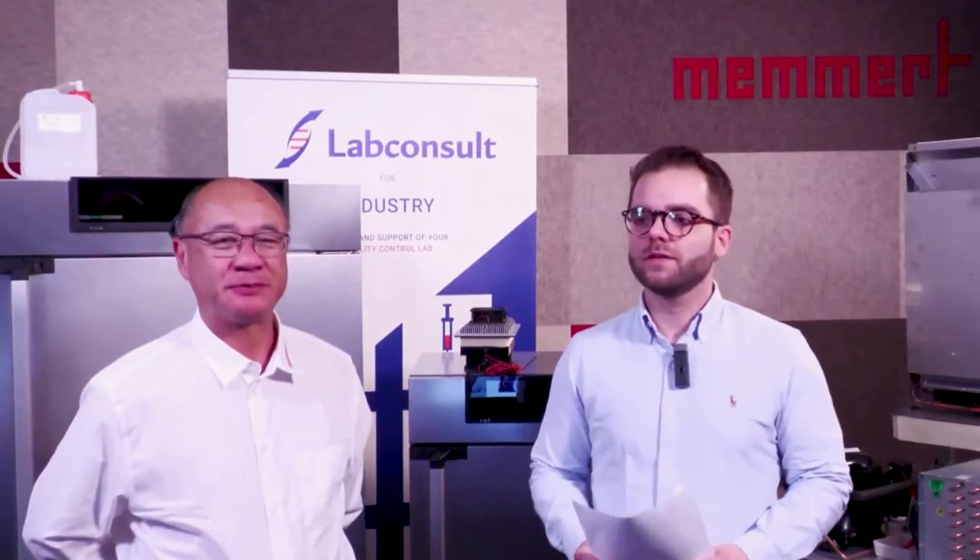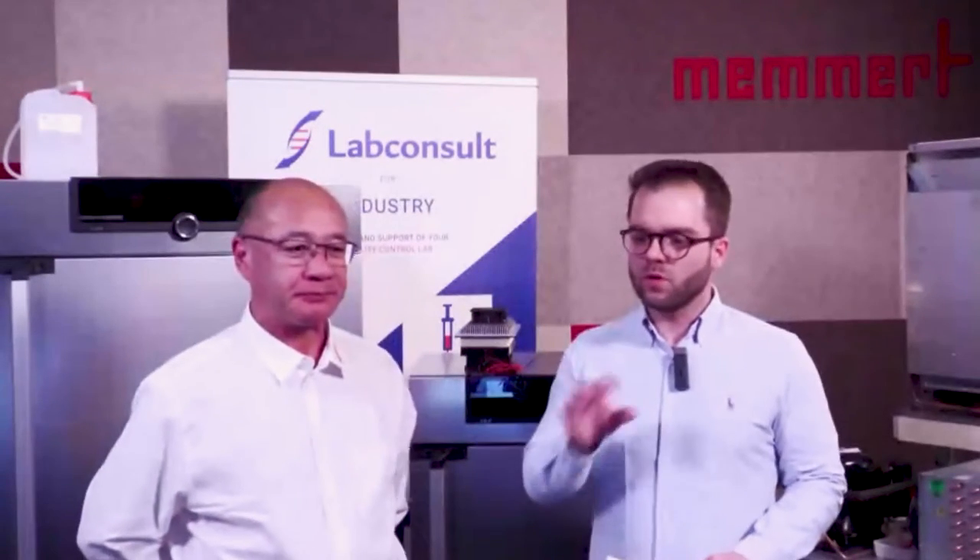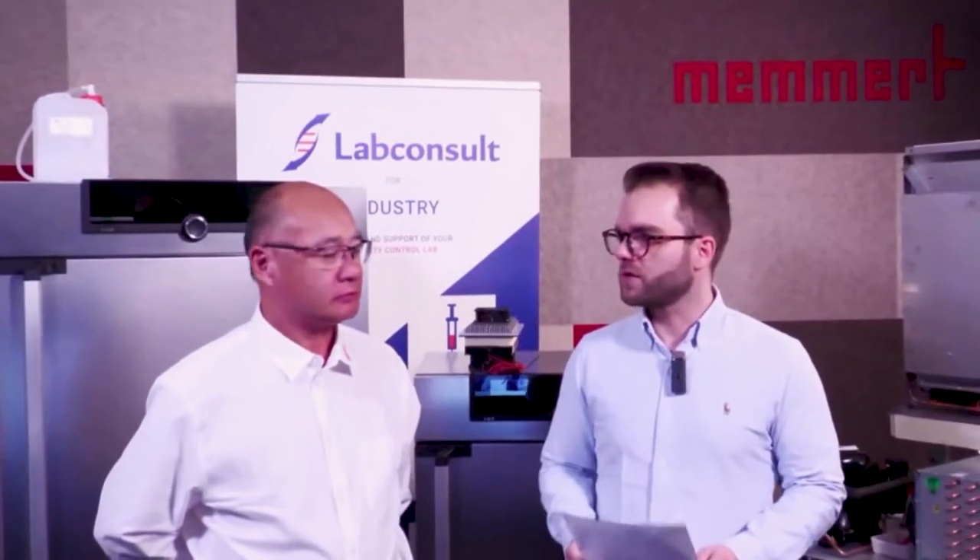I've gathered some questions that my customers asked me — first about climate chambers and then about the incubators. The first question is about lighting: is it possible to have UV light inside, and is it possible to control the intensity of the light? For other devices, light is an accessory. If you need UV light, it is available in a compressor technology climate chamber called ICHL, which can have a box with white light and UV light. This light works on or off — it is not possible to modulate the intensity.